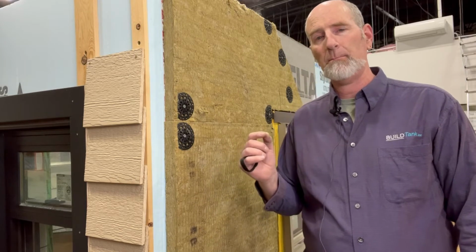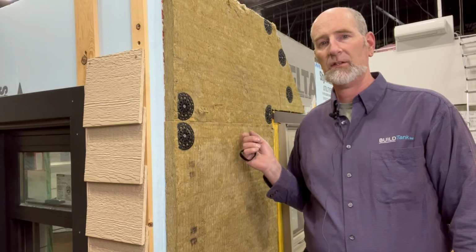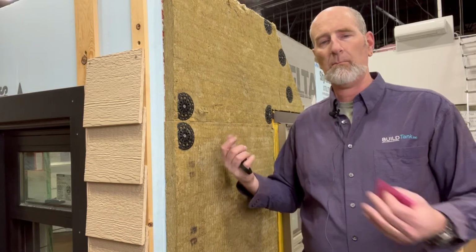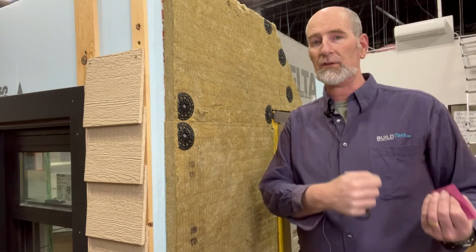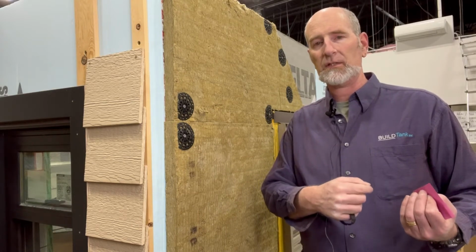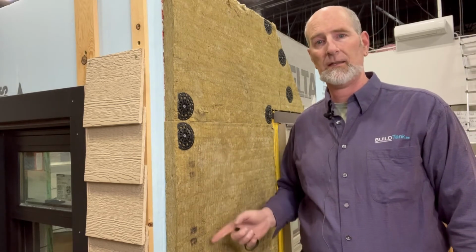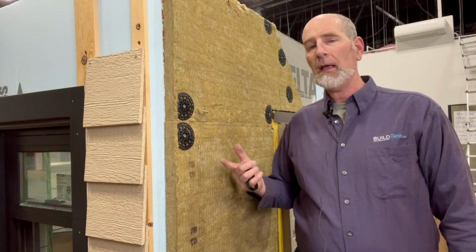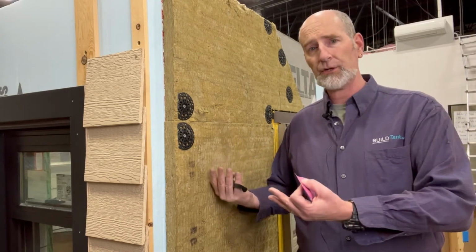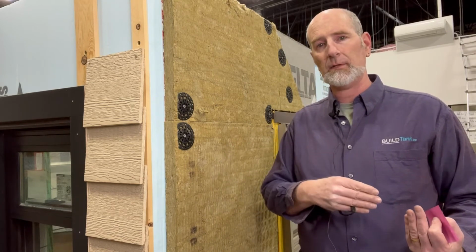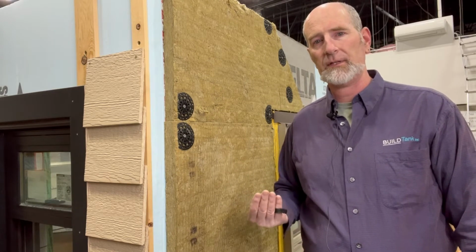Now, the next thing we want to talk about is condensation and condensation risk. And the ability to overcome that risk is to use a continuous insulation. So condensation happens when moisture gets inside of our assemblies and that moisture hits a cold surface. So the first condensing surface is the coldest surface inside of this assembly, which is our exterior sheathing material. Now, I can stop condensation by two means. I can try to ensure that moisture isn't getting into the assembly, or I can raise the surface temperature of that first condensing surface there.